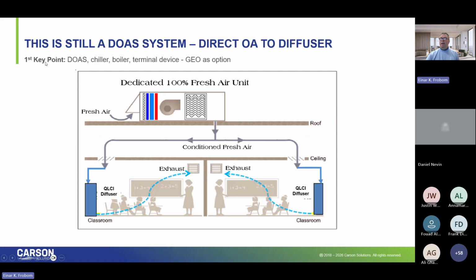So key point number one, this does have a DOAS unit applied, and typically a chiller, typically a boiler, and then our terminal device. And for those that are on the call that have done DOAS units, this is not a big leap of faith in terms of the technology. The only real difference is that we're ducting directly to the terminal that is in the classroom. And then the biggest difference is how that air is introduced to the space, moves through the space, and then is ultimately exhausted. So that's really the difference compared to other DOAS types of systems.